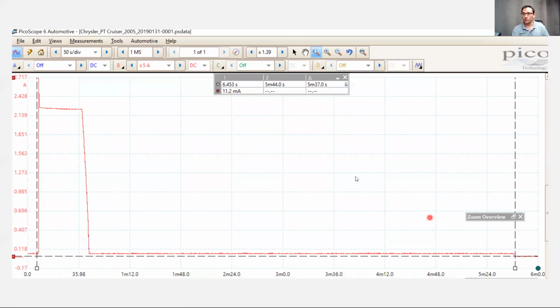Towards the end, I got down to 11.2 milliamps on my low current clamp. You understand I told you I have a variance of plus or minus 25 milliamps in my testing. So I'm confident that 11.2 milliamps, even if my meter was skewed the wrong way, plus 25 milliamps, is well under the 50 or 60 milliamp draw that I expect to have. I'm confident my result is going to leave my customer in a good place.